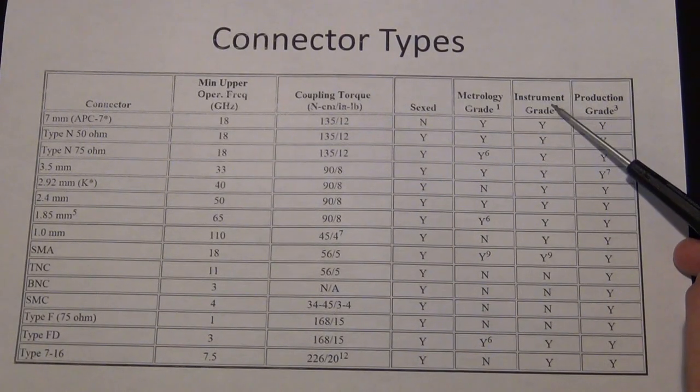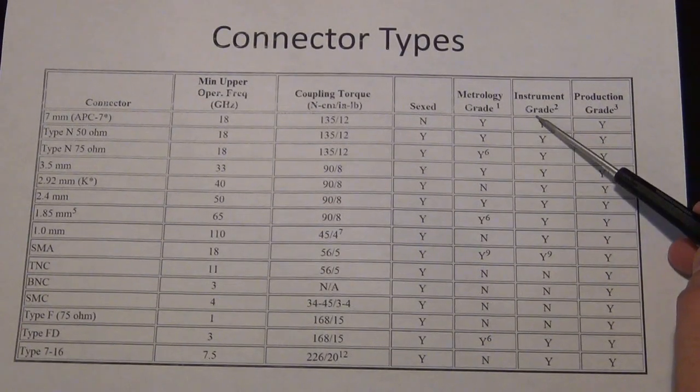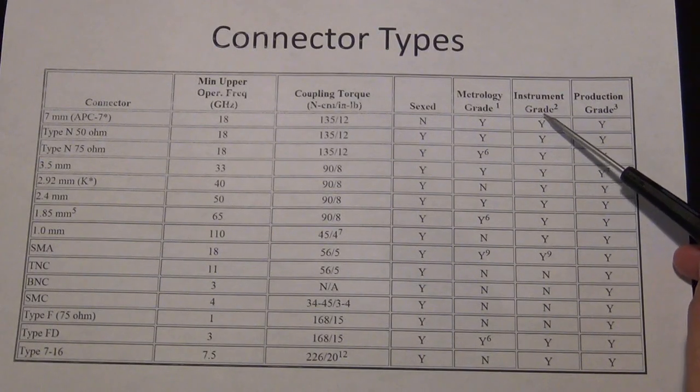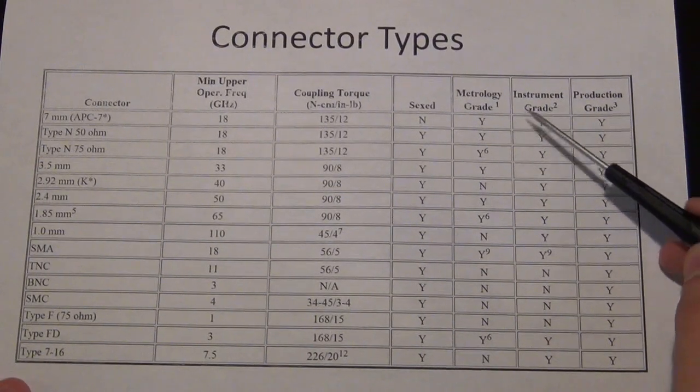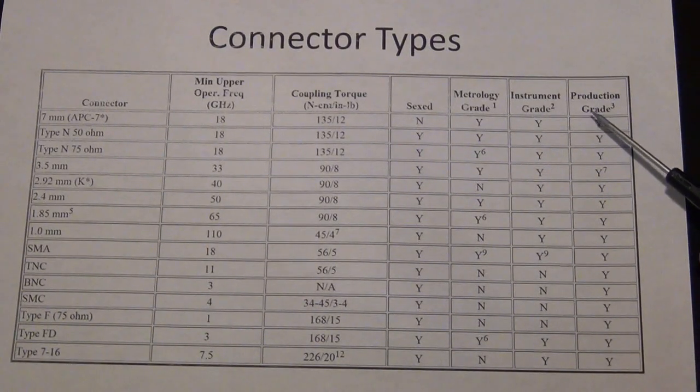Instrument grade connectors are also very good, but they sit in between production and metrology. So here you're doing somewhat sensitive measurements. They have fairly tight tolerances, they have very good performance, and they last a long time, but they're not as good as metrology grade.